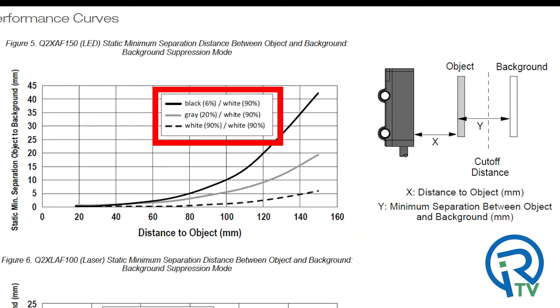For the Q2X series, banner shows three different reflective materials. Even though the sensor is looking for the angle of light being reflected back, there is still some difference in the amount of separation from object to background depending on the color reflectivity of the part.